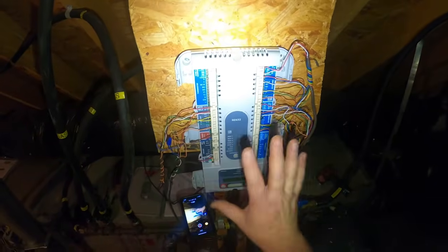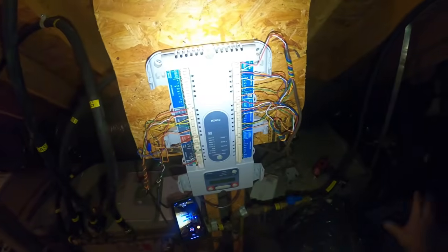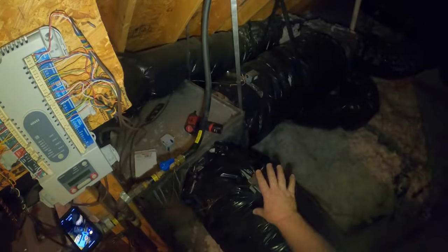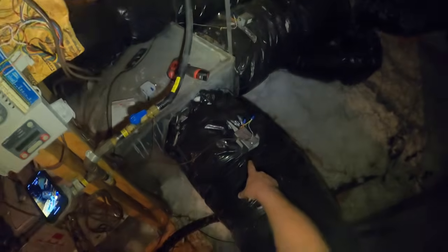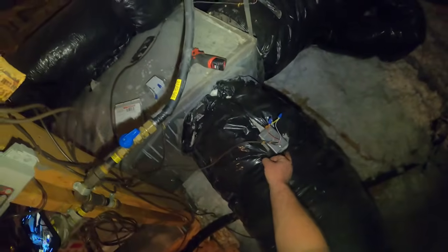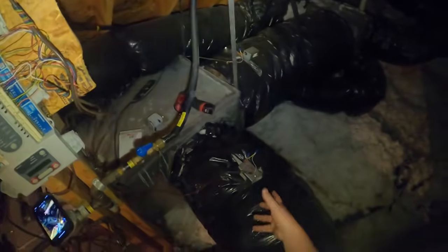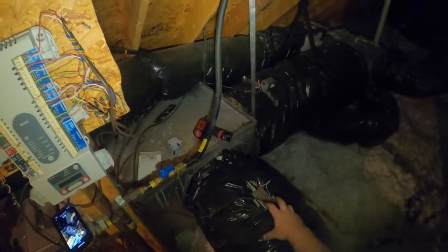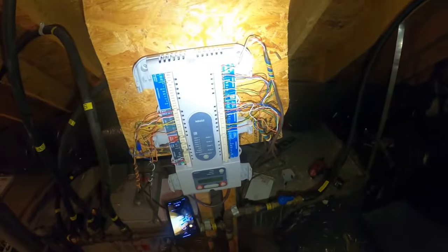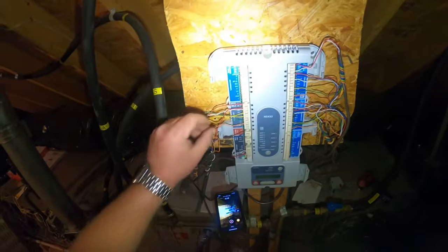A secondary transformer is going to power your thermostats and your damper motors. These are damper motors that power close and spring open. The old Honeywells are still here, the metal box. We all know probably three weeks after we leave here, one of these is going to stick closed, and then the other one's going to stick closed. That's what happens. The spring corrodes in them. After a while they lock up, and it'll close, and then it just won't unwind and spring back open when that voltage is dropped from the thermostat for that zone. So you want to keep an eye on these kinds of damper motors. They stick on you a lot.